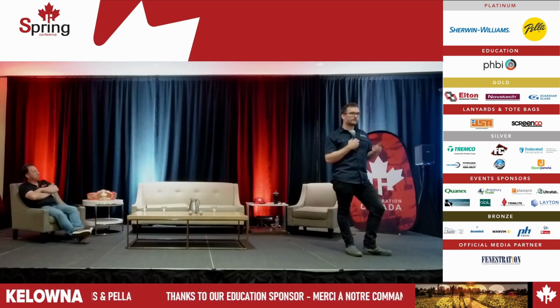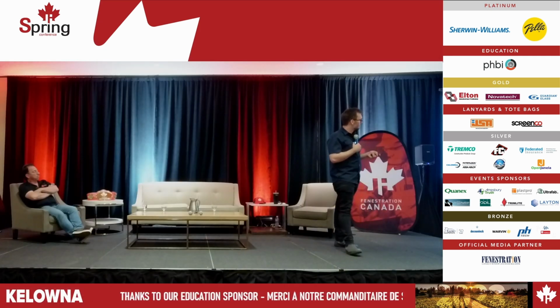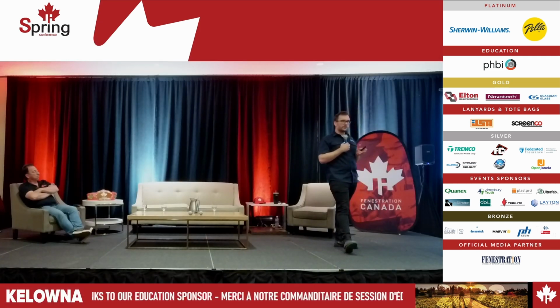On our adjusted thermal energy demand intensity, our percent improvement for the mechanical and system goes from 12.2% up to 19.7%. That's a 7.5% increase in energy efficiency on our mechanical and system metrics. Our thermal energy demand intensity drops from 49 to 43. That's a 6 kilowatt per hour per year decrease. That's another energy improvement just by having the majority of the windows facing south.